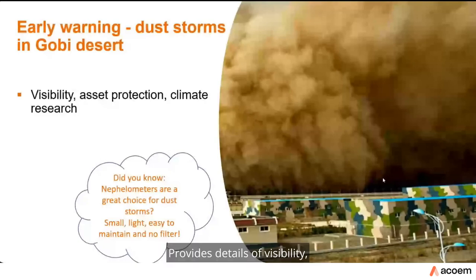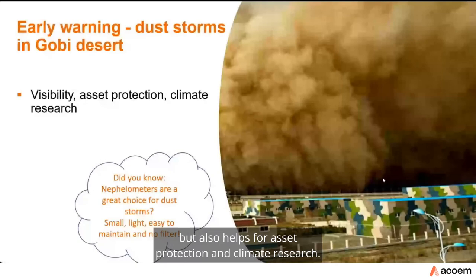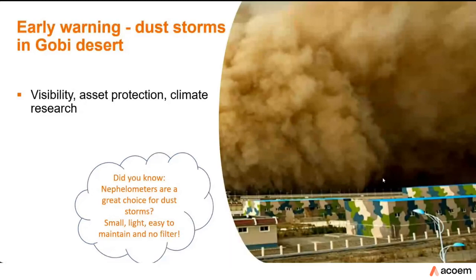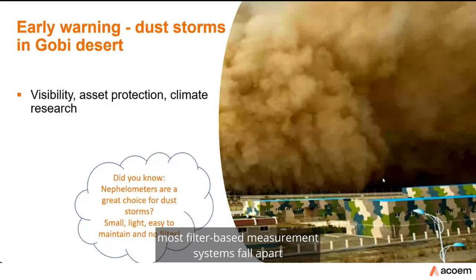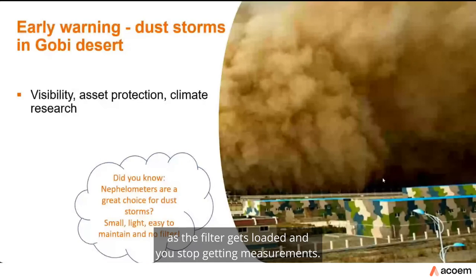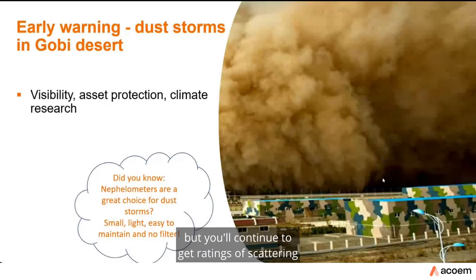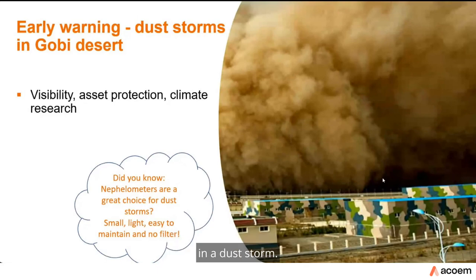Another application is dust storm monitoring. In the Gobi Desert, dust storms move across China and there is a whole monitoring network providing an early warning system for visibility, asset protection, and climate research. Typically in dust storm areas, most filter-based measurement systems fail as the filter becomes loaded, whereas the nephelometer can read very high measurements for quite a long period of time, continuing to get scattering readings well after most instruments have stopped.